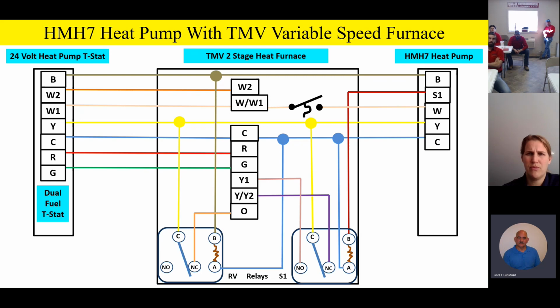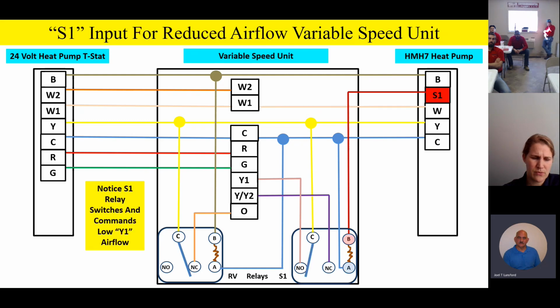So when the outdoor unit says to the variable speed furnace or air handler, either one, "Hey, give me reduced airflow," it's going to energize S1 just like we did before, bang. And you see that S1 relay switches. Now we're still in the cooling mode, it's just reduced airflow now. The unit is calling for reduced airflow. That S1 relay switched. We have reduced airflow and we're cooking along at reduced capacity.